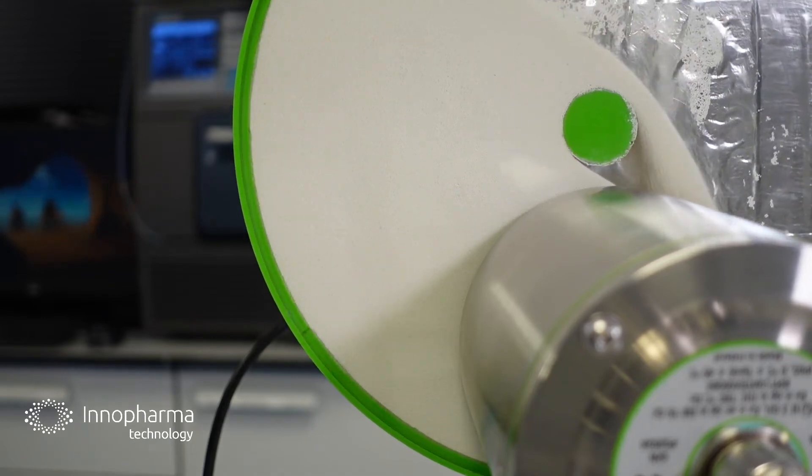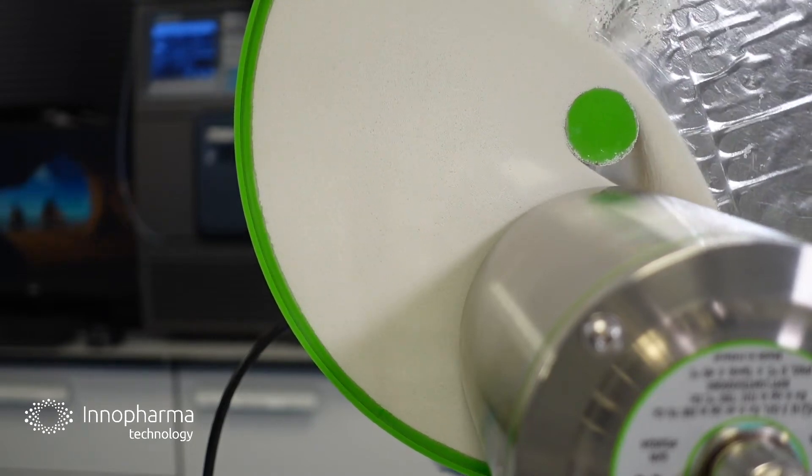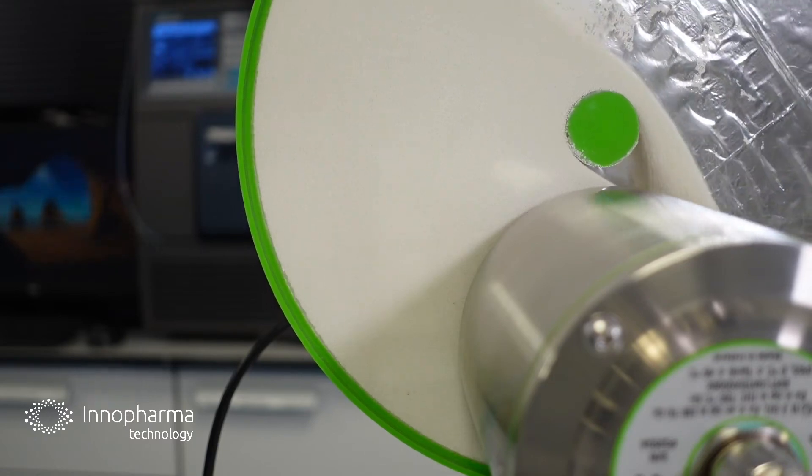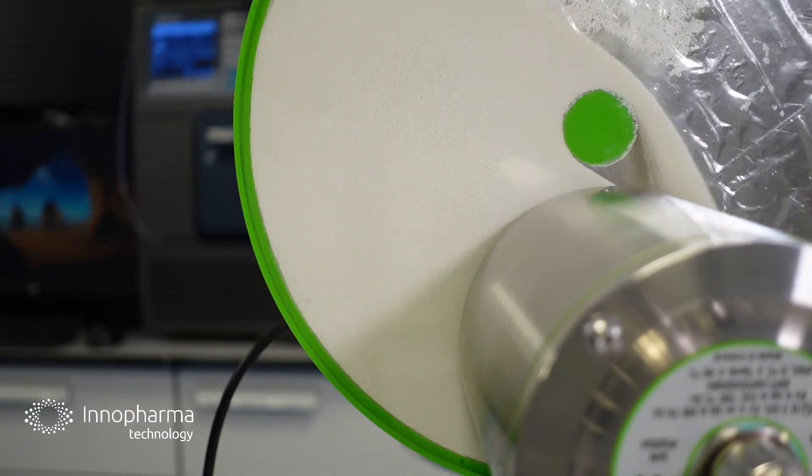But going back to the I-PASS 2 here looking inline, if we take a closer look at what it's doing, it's getting presented with new material every couple of seconds from the spinning wheel, very similar to something like a fluid bed process. This is actually cellets or coated material that we have in this drum.